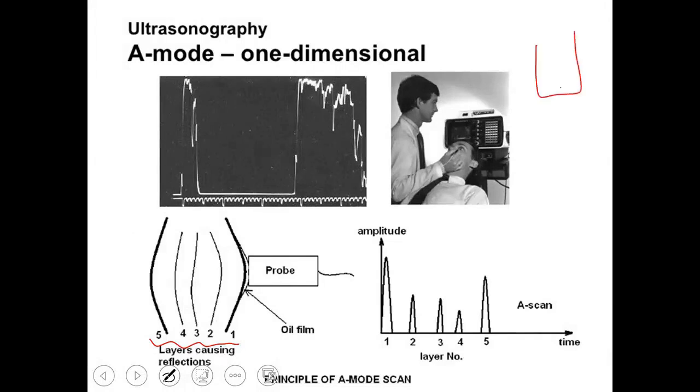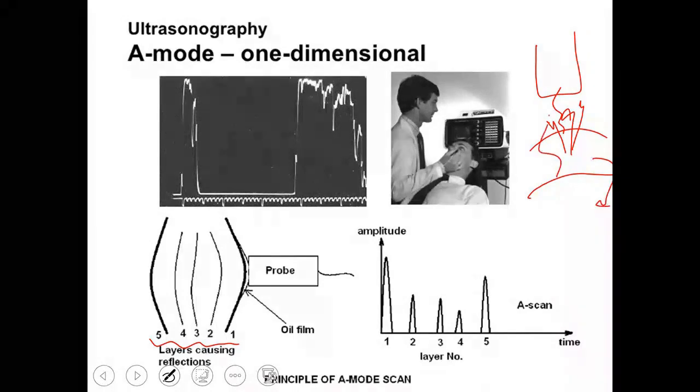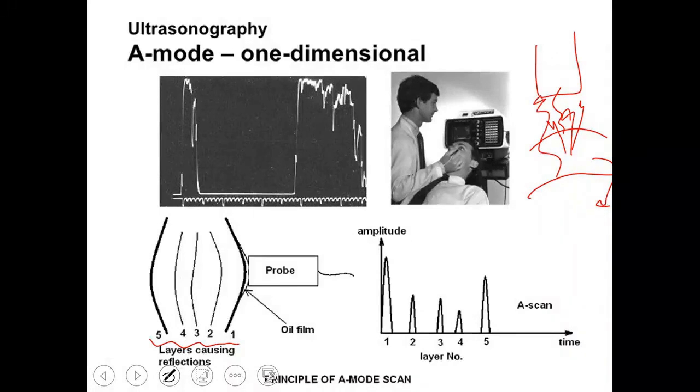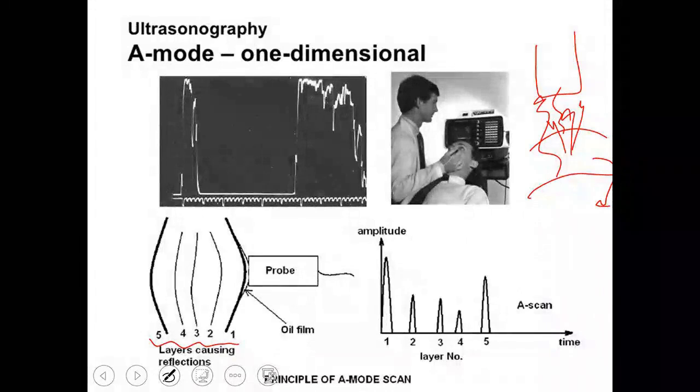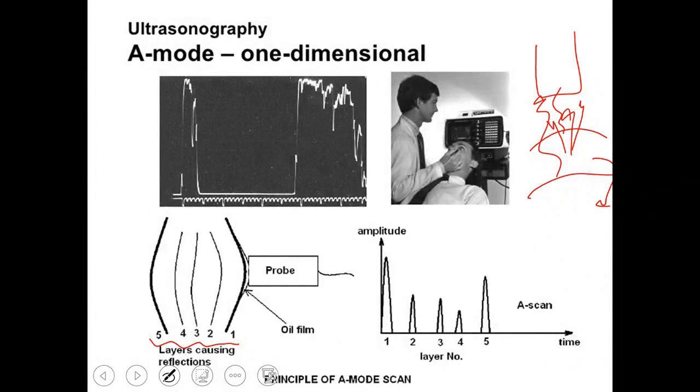The idea in ultrasound is that the transducer transmits the pulse. This pulse undergoes transmission within the tissues present, leading to various interactions. If it encounters an interface, it will reflect, and the transducer will start to receive this signal and translate it. Reflection occurs, of course, depending on the subject in between. So if my ultrasound pulse is coming, reflection will happen from point 1.